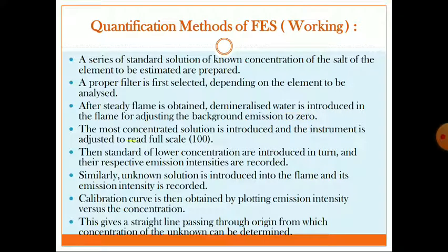Then the most concentrated solution is introduced and the instrument is adjusted to read full scale 100. That means from the above standard solutions, the most concentrated solution is used and kept as the sample, and we make the instrument read full scale 100. That means it is set to 100% emission intensity. Then the standards of lower concentration are introduced in turn and their respective emission intensities are recorded.